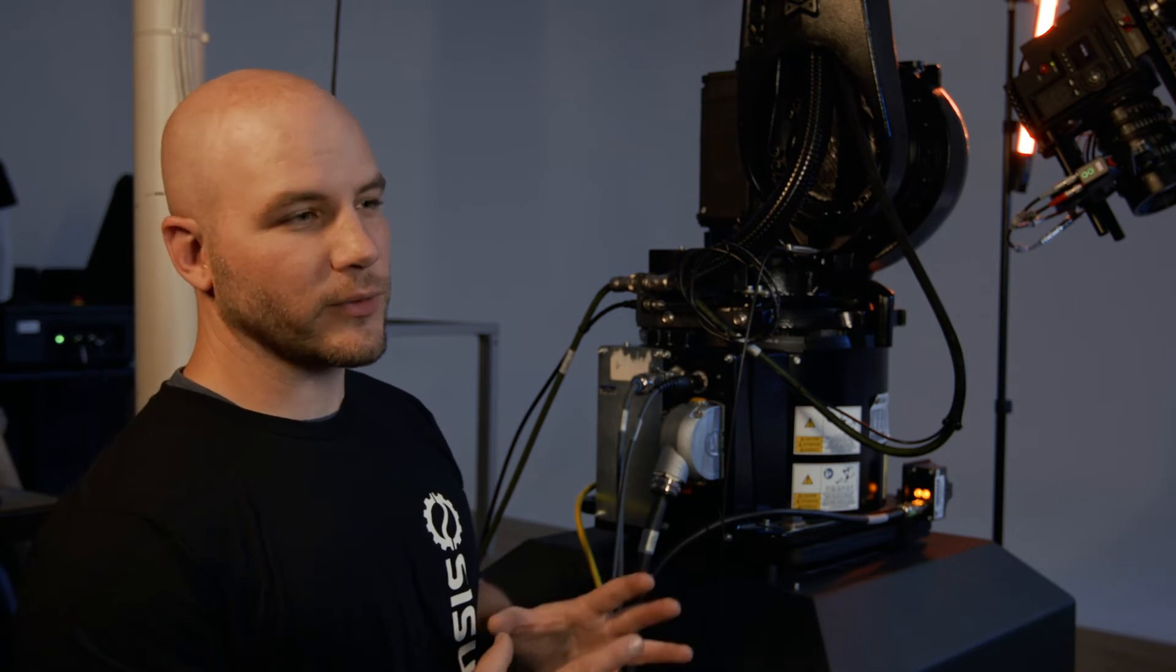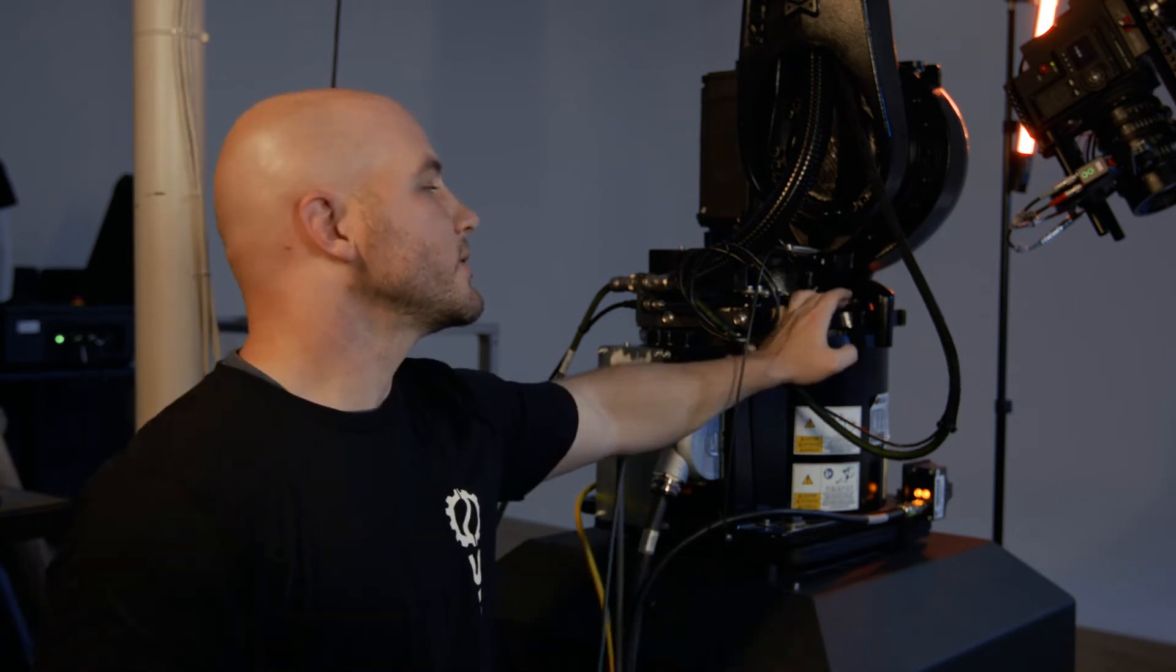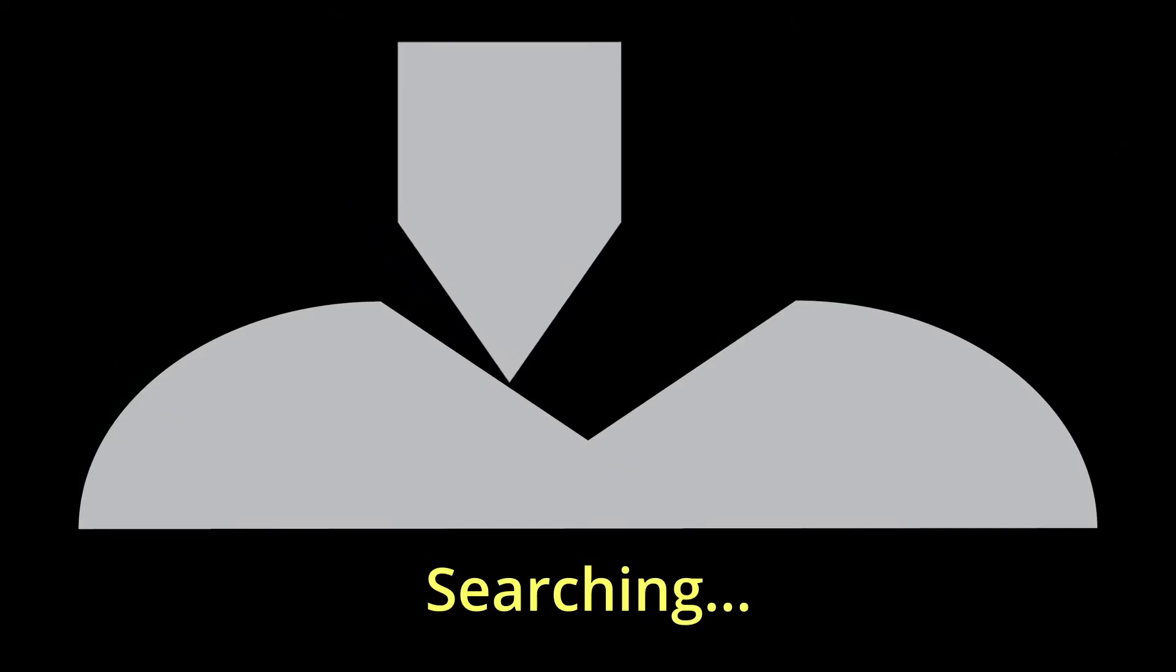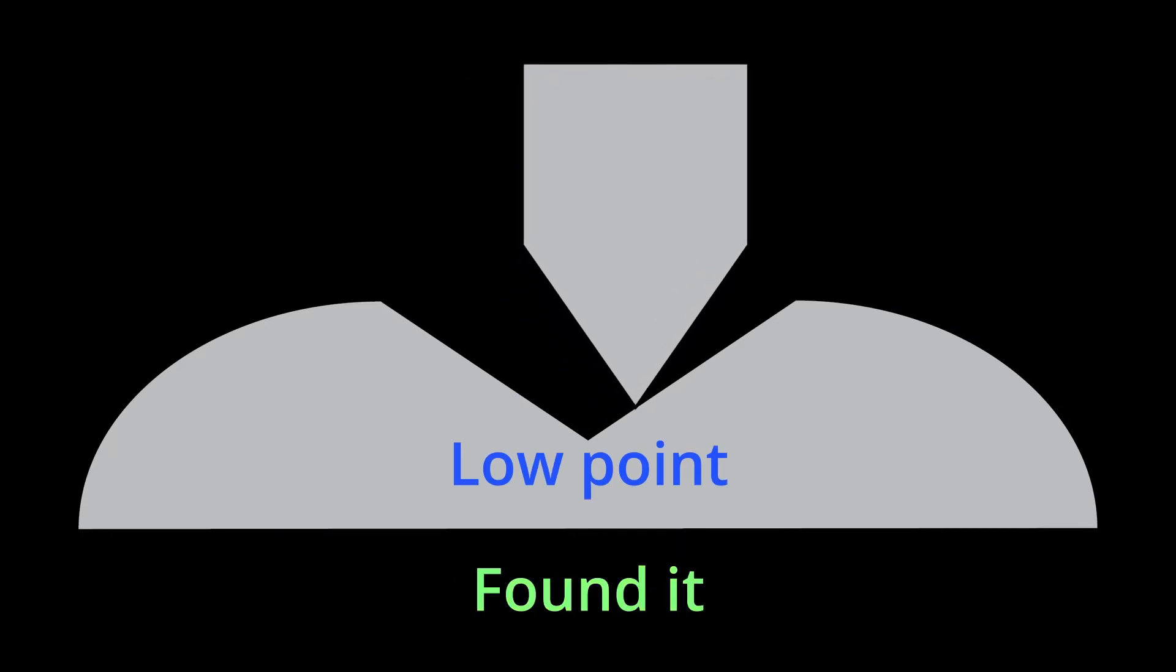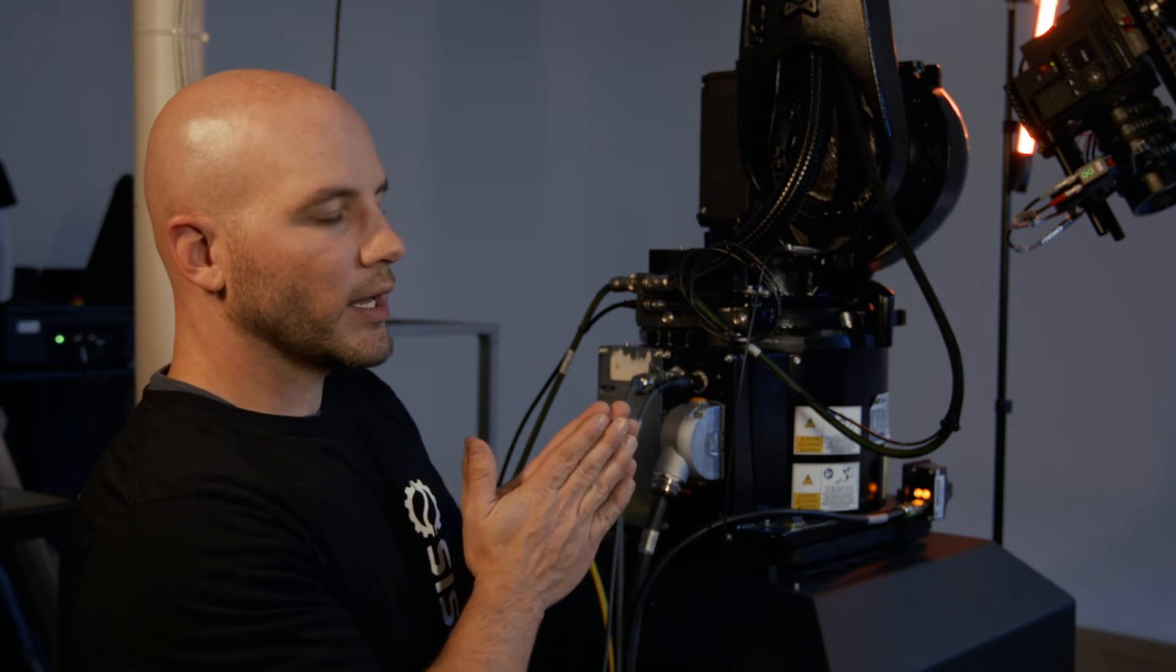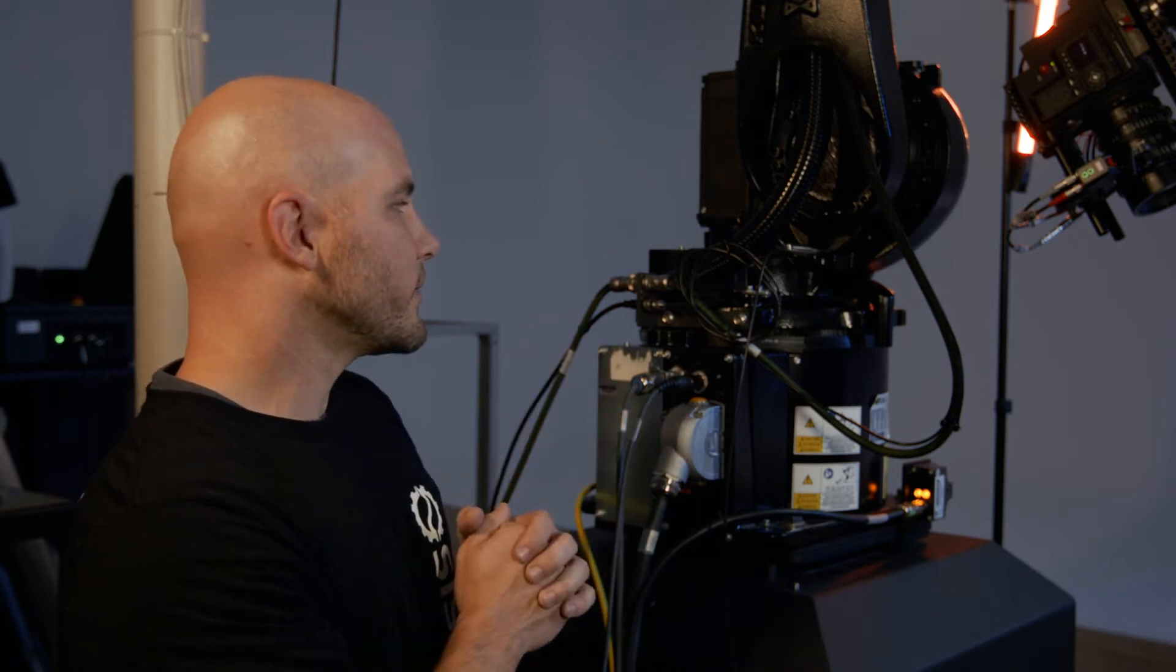Before we jump back into the remastering process, I just want to talk you through what we're actually doing here. As you can see on this back metal piece, there's a groove and the probe is going to look for that valley on that groove. So it's going to move a little bit to the left and right so it can know exactly where that low point is.